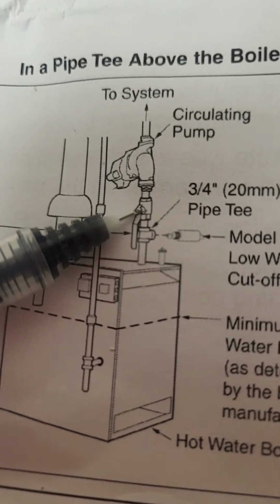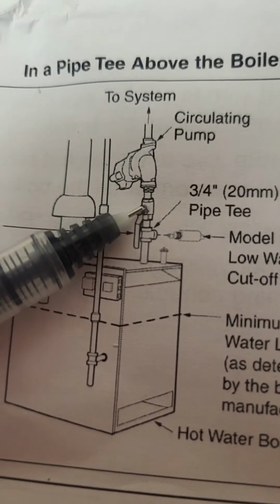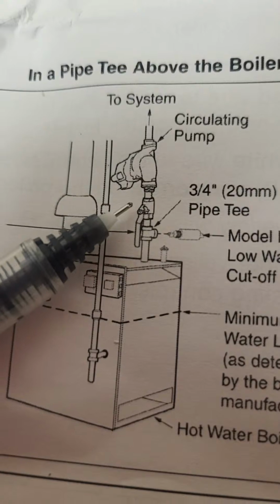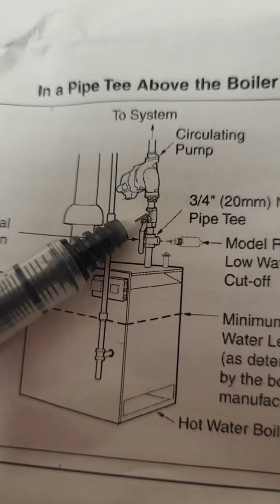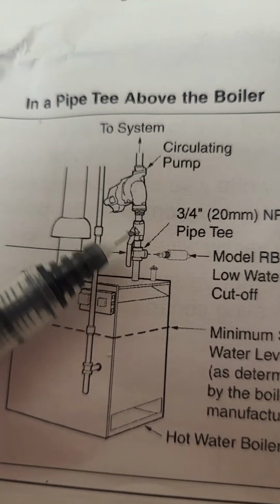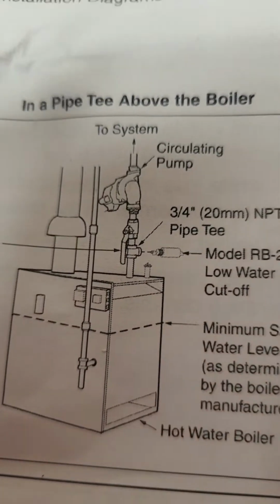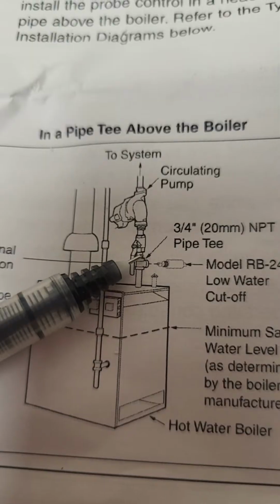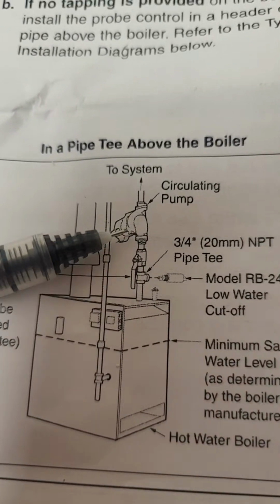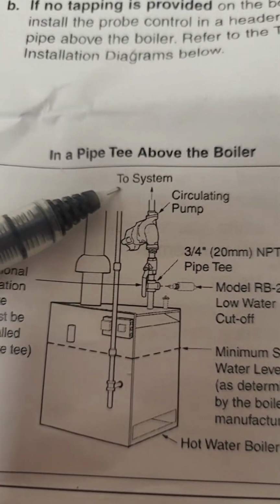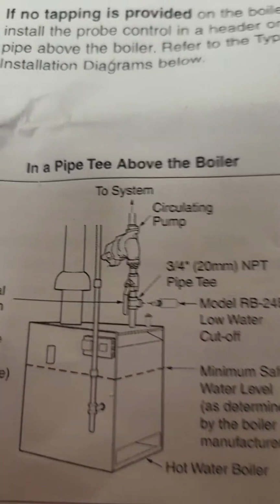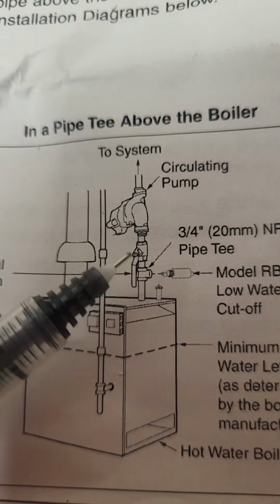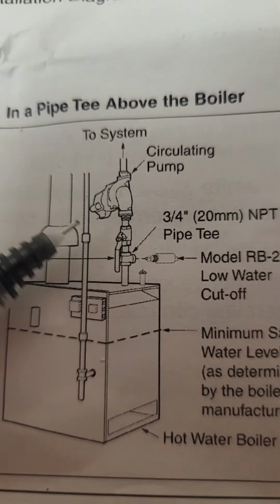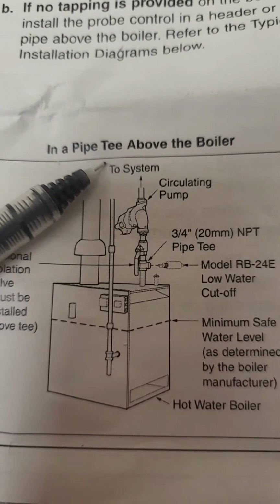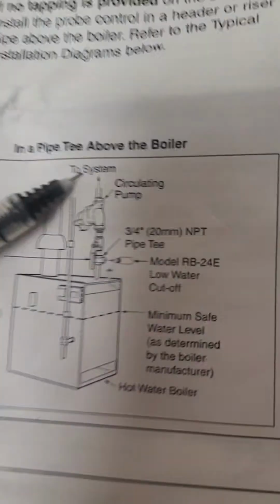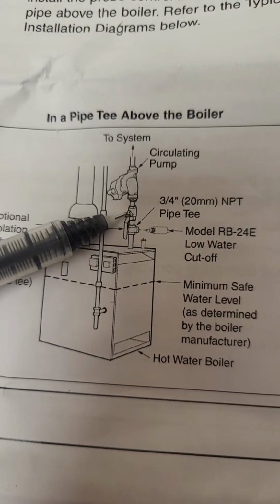They want you to put the isolation valve on top of the T. In practicality, guys, if you need to replace this low water cutoff in the future, you can just turn this out. If you have an isolation valve, you can turn that valve off, and it's going to take way less time to drain the water down from the boiler and purge air from the boiler, because everything from the top of the boiler going to the house, to the system, is already valved off. This isolation valve is nothing more than that. If you can install it, it's going to save you a bunch of time with servicing. That's why in the pipe T, meaning what I drew on the board, above the boiler, this is what they recommend you guys do.